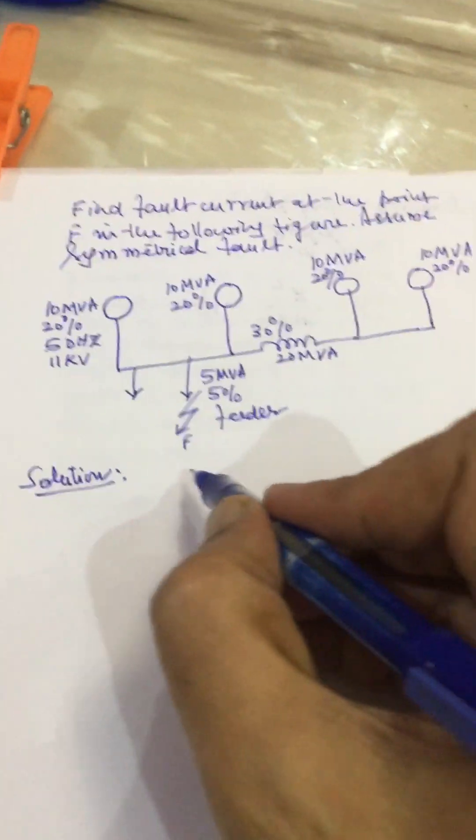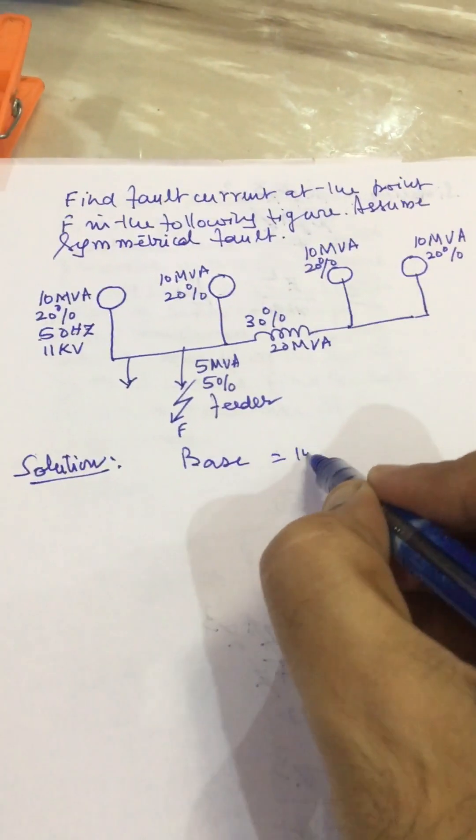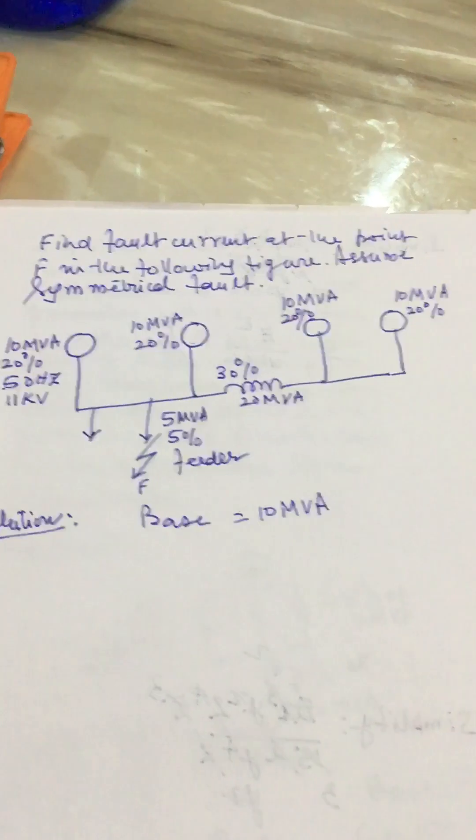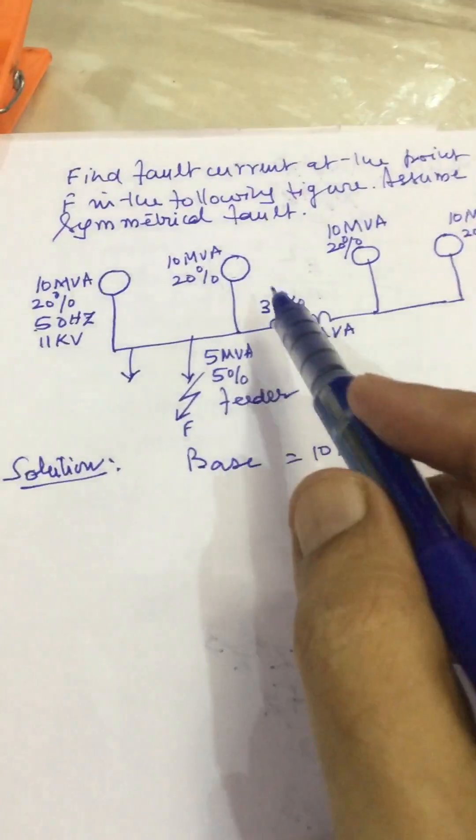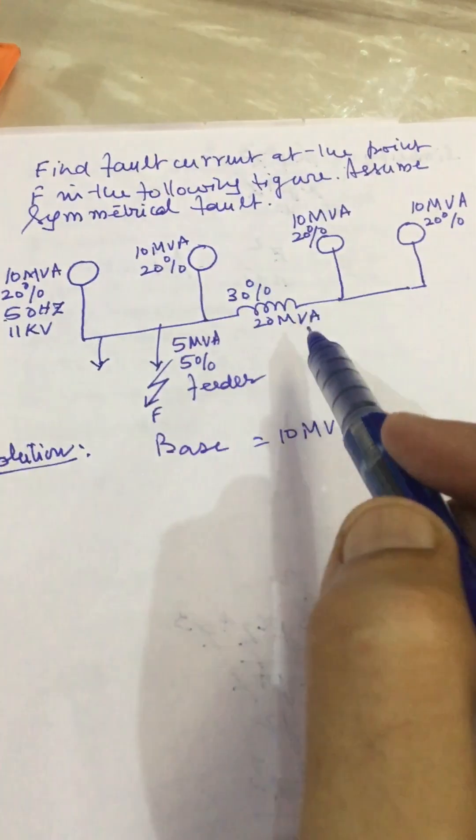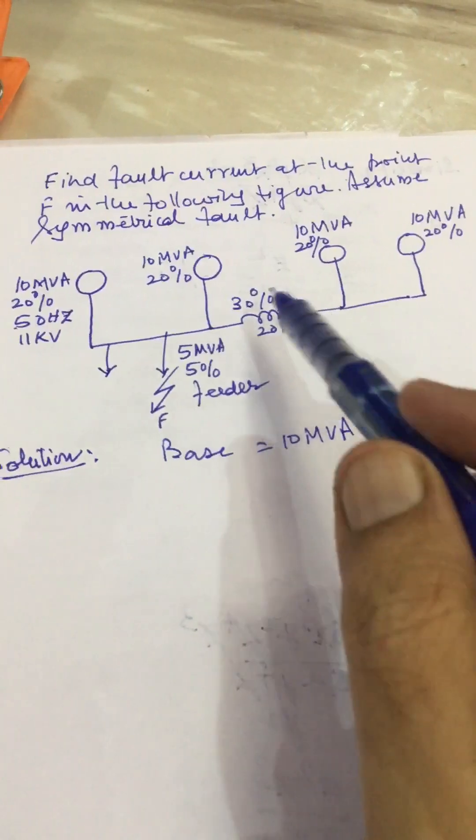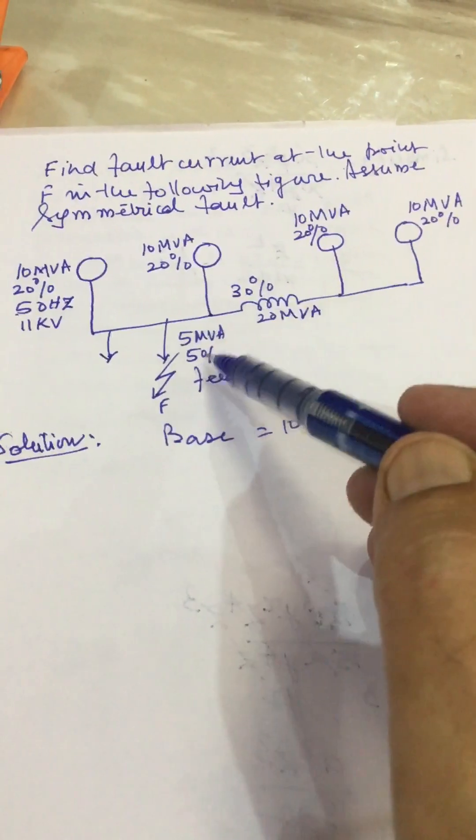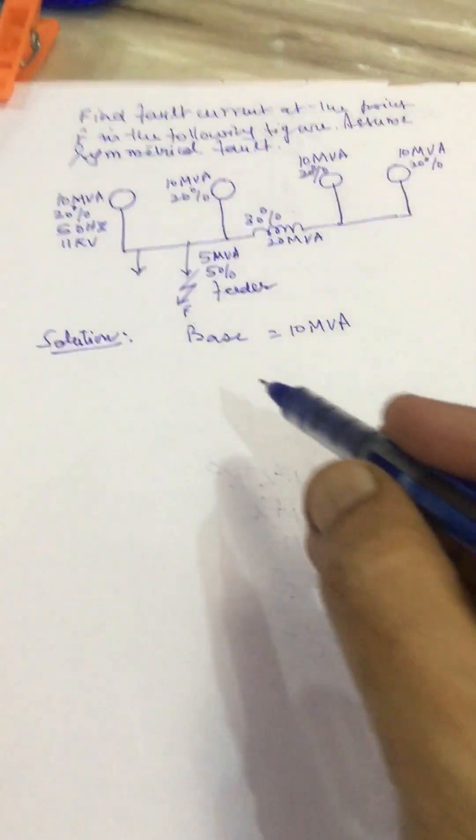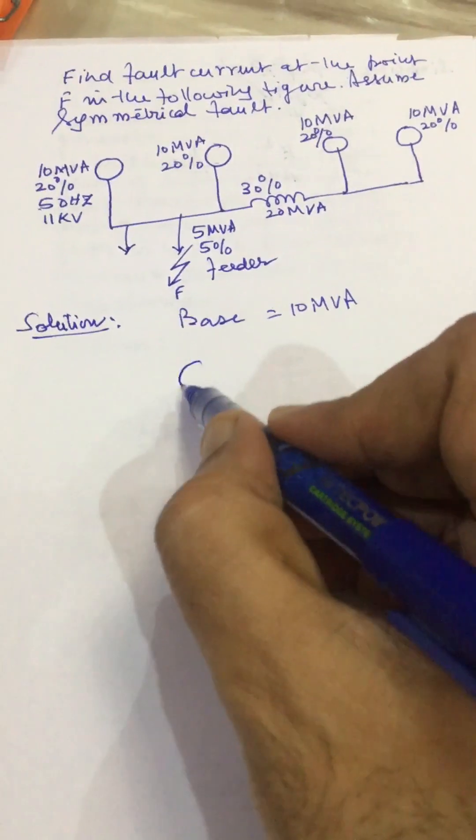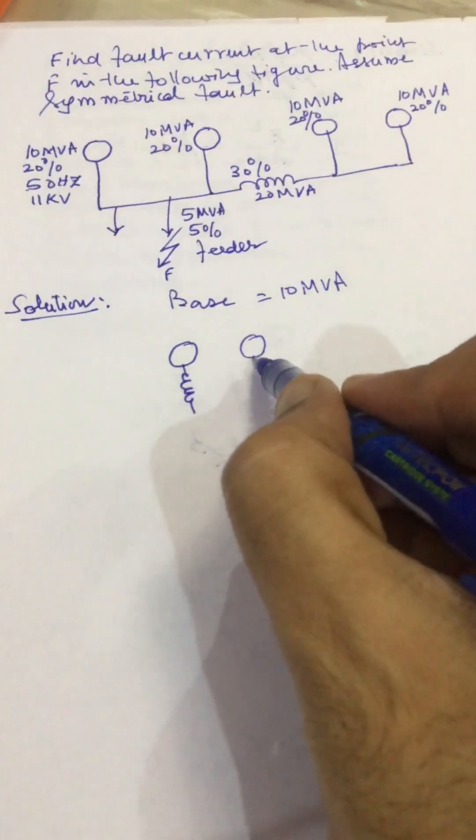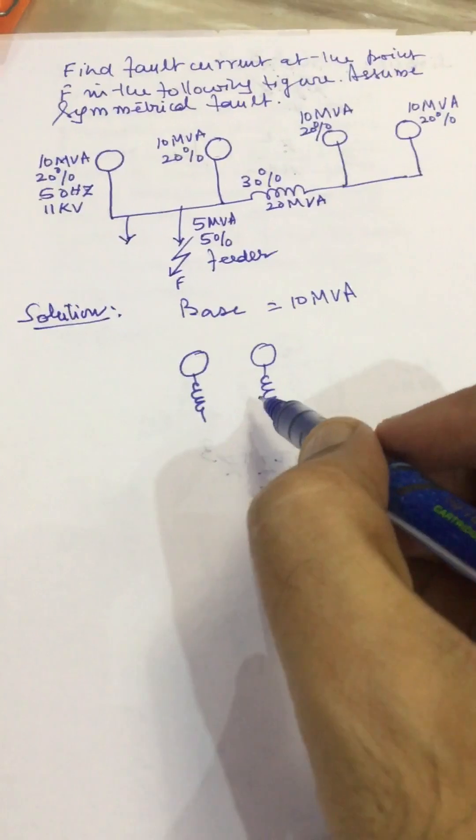Base we will assume 10 MVA, because these generators are rated as 10 MVA, we assume base as 10 MVA and these reactances will remain same, only thing we will have to change these 2 reactances to base 10 MVA. From this we can draw the following single line diagram or reactance diagram.